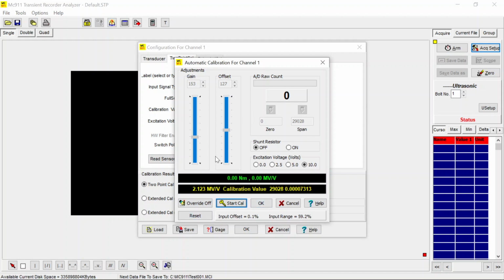So they have different resolutions. In case you have difficulty, if one of these sliders goes to one end, you can reset it just like this and recalibrate again, and call start cal. It goes back and forth and calibrates again. This is another way of doing it in case there was no cable connected and it goes all the way to one side. Then you connect the cable, come back, reset it, then start cal. That's another way of doing it.